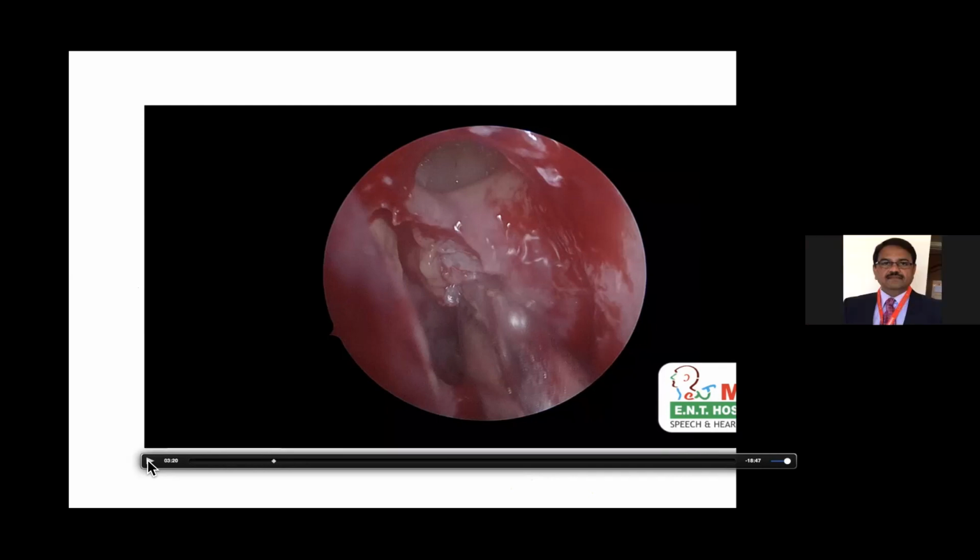Important point. For a safe surgery with the debrider, the speed should be high, not low. Another important point. Speed should be high. What speed are you keeping for this, sir? 6,000, oscillation. Forward 4, reverse 2.